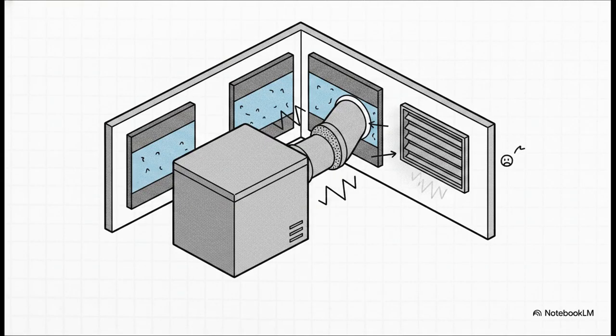And speaking of that toolkit, let's look at the three-part defense they use to lock down a super noisy air handler sitting in a mechanical room right next to an occupied office. First up, if noise is riding the ducts, you drop in a special version of a duct silencer shaped like a 90-degree elbow. Second, if the noise is just blasting straight through the drywall, you deaden it by installing acoustical wall panels. These bad boys range from 2 to 4 inches thick, featuring a layer of fiberglass sandwiched between a solid metal outer wall and a perforated metal inner wall for maximum absorption. And third, if that mechanical room happens to be near a sensitive outdoor space, noise might actually bleed outside. To shut that down, you use special acoustical fresh air louvers to dampen any sound trying to escape the building.